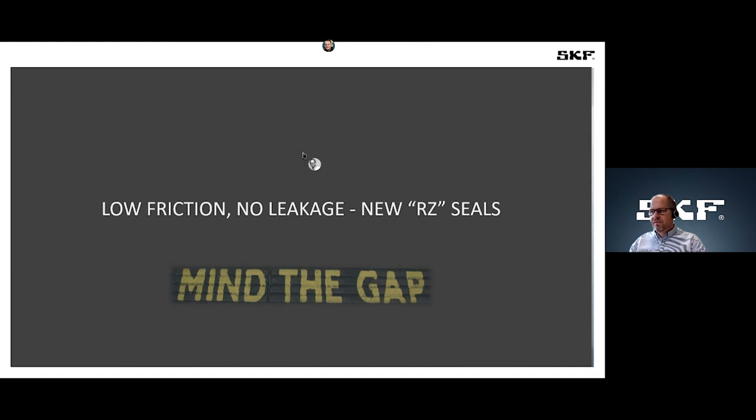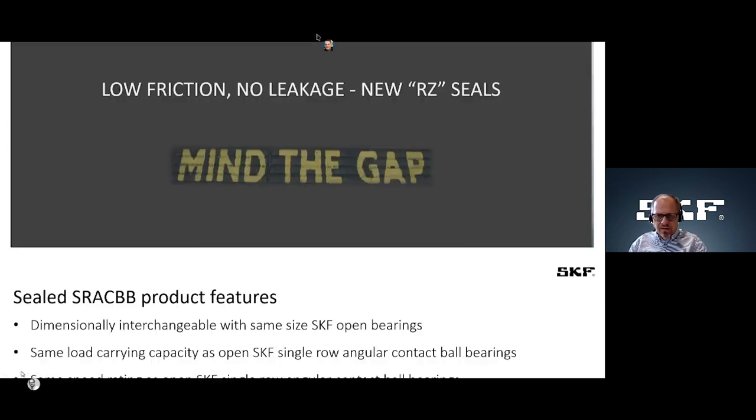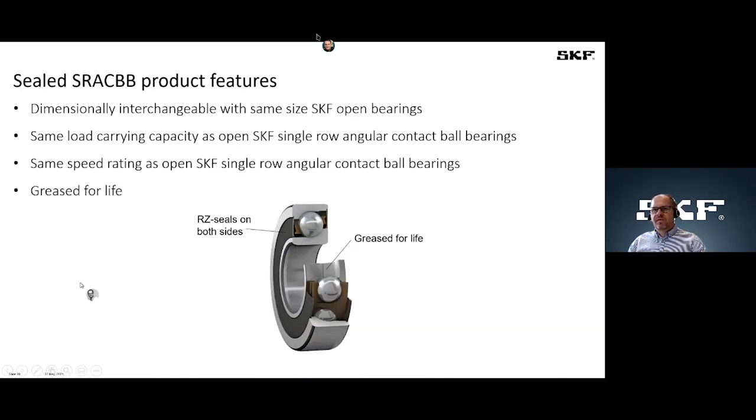Thank you Paul. So I will give you some news about our sealed angular contact ball bearing. So sealed angular contact ball bearing we introduced several years ago for the market. We equipped the angular contact ball bearing with two seals on each side. And as we use a non-contacting seal, we have the same load carrying capacity and the same speed rating like for the open pendant. So it's easy to interchange an open bearing with a sealed one. The bearings are greased for life.